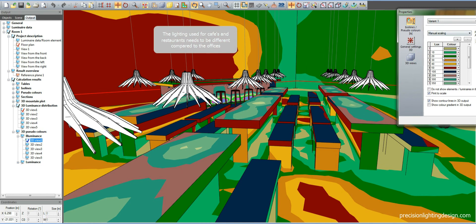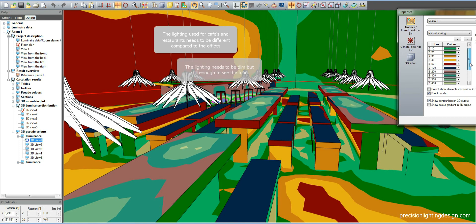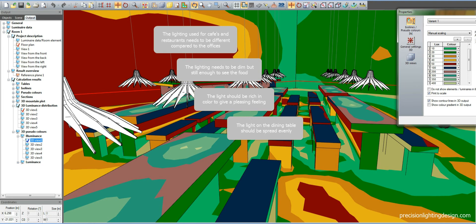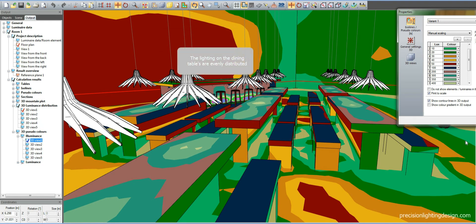The lighting used for the table needs to be different for cafes and restaurants compared to offices. The lighting on the table needs to be dim but still enough to see the food. The light should be rich in color to give a pleasing feeling. It should be spread evenly on the table for better visibility. As you can see, the lighting on the tables is distributed evenly, with 200 to 350 lux on the table.